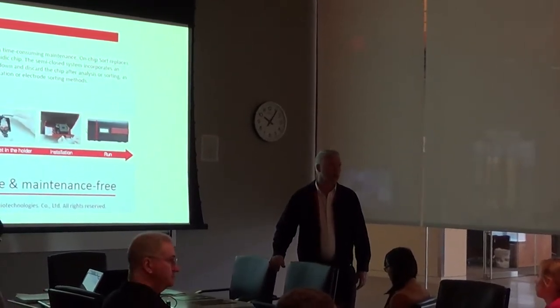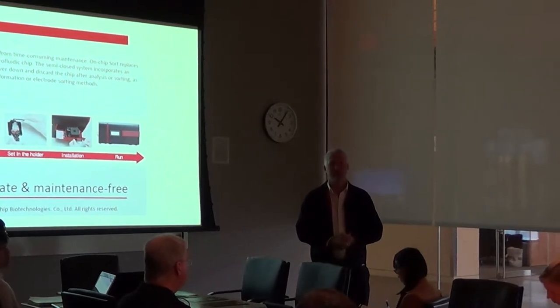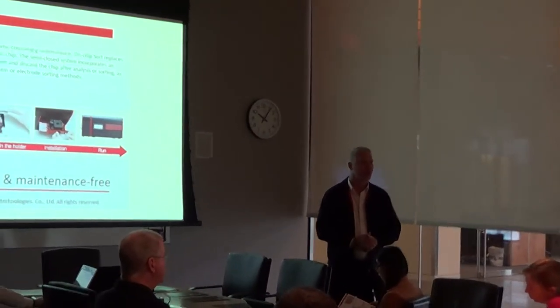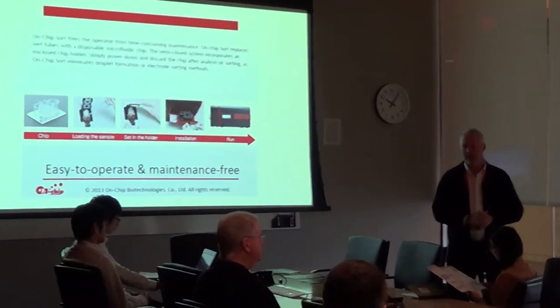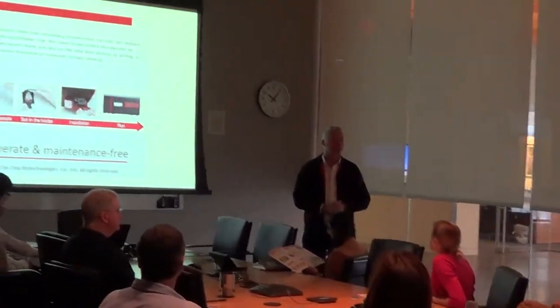The on-chip sorter is all about damage-free. The major deliverable of the instrument is that it's 0.3 psi, which is lower than the osmotic pressure in the eye, I'm told. So pretty interesting in that way. We're the only true microfluidic sorter on the market, and we're really the number one damage-free offering right now.